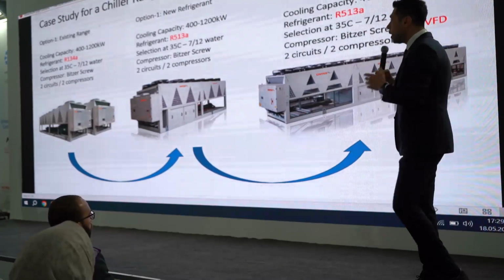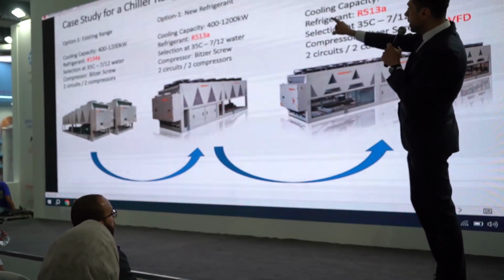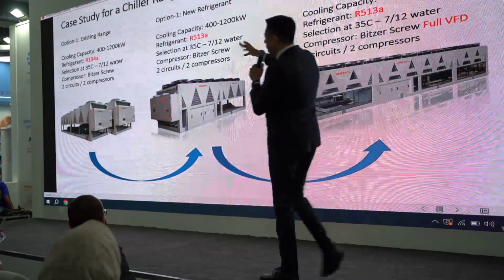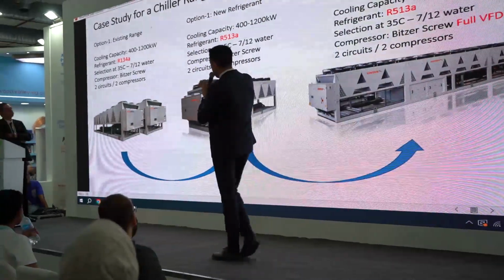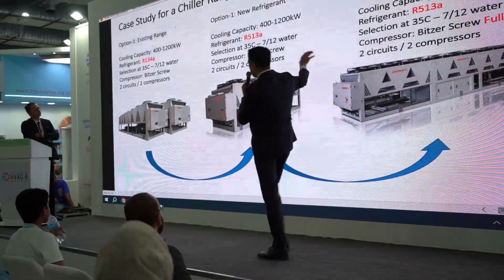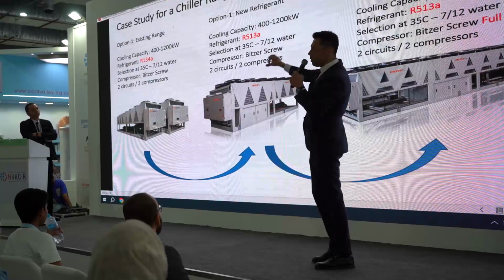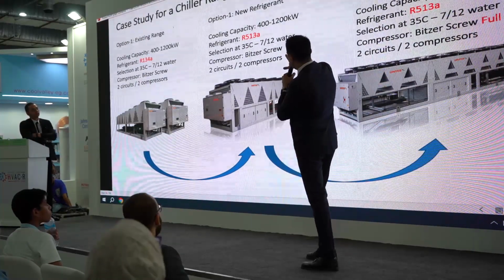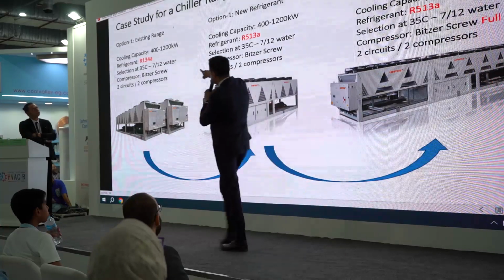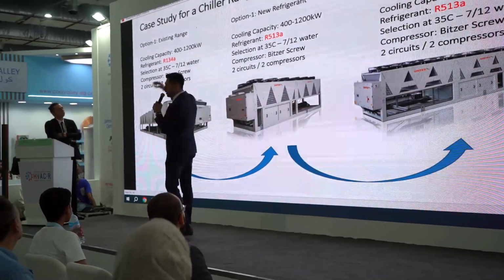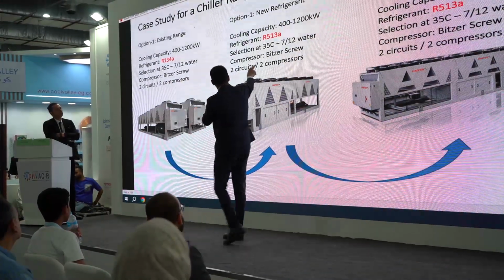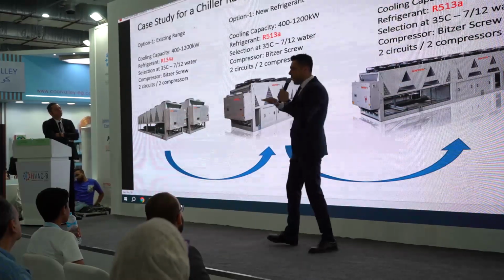What does this mean? So, in the first part, an existing range of, for example, around 1000 kilowatt of chillers with the same compressor. I put 2 circuits, 2 compressors. Same thing, same conditions with some differences. The first part is with 134A refrigerant, the existing one. The second part is the 513A, same thing.